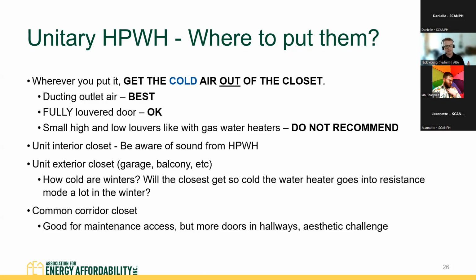The best approach is to put it somewhere inside the thermal envelope, but get the cold air out of the closet. That way it's always operating in heat pump mode efficiently, because it won't be exposed to extreme outdoor cold. If you can get the cold air out of the closet, you'll be okay.